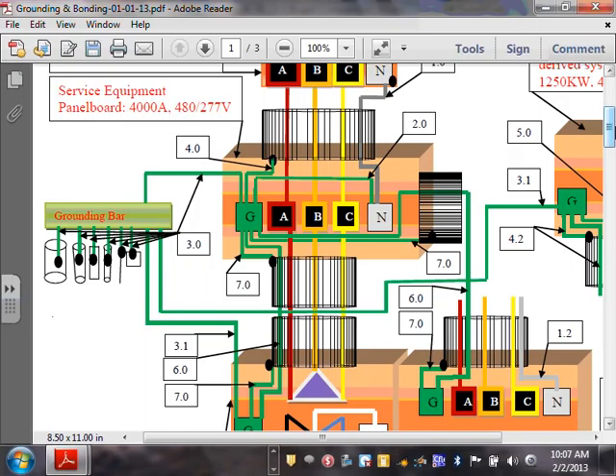The other method, if you like to terminate and cut wires a lot, is you go one conduit at a time. You take the first 4-inch rigid and you ground it to the grounding bar, and then the second, and then the third. These are home runs, one from every conduit into the ground bar. Anybody does it this way? The code allows you to do it. Either way, any method. But typically what we do is we group them all together. Any comments, guys? Any questions about this? Comments, questions? Does it make sense? No? Am I beating a horse that you guys know? Okay, all right, so we got that.